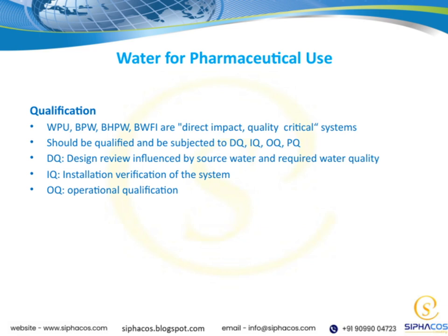Finally, PQ, or performance qualification, confirms that the system consistently produces water that meets the quality standards throughout its operational life. Operational considerations are also key because maintaining water quality for pharmaceutical use requires continuous oversight and validation.